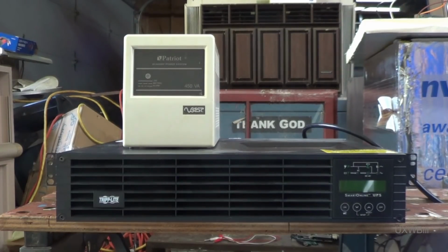When these are operating normally, everything plugged into them is running from the inverter all the time. This provides very effective isolation against power line events, including severe overvoltages and spikes of far too short a duration for an uninterruptible power supply to normally be able to intervene. And so it is that these things provide for very effective filtering from power line occurrences getting to the equipment that's attached to them.